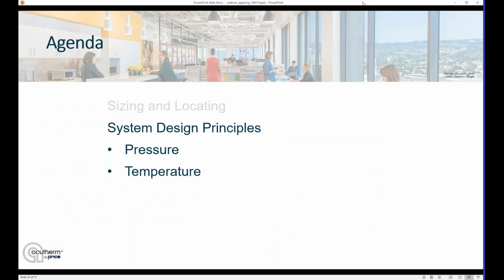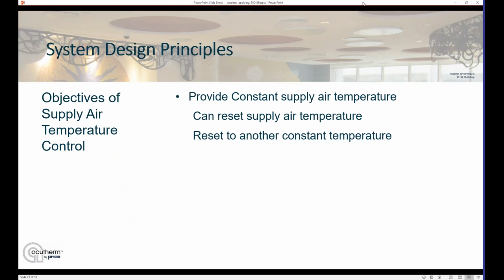That talks through the pressure control. Let's move on to temperature. So our objectives of supply air temperature control here are, 1, to provide a constant supply air temperature to the diffuser. Now that's not to say you can't reset the supply air temperature. It's just that what we're looking for is to reset to another constant temperature. The diffuser is trying to control the air volume to maintain temperature in the space.